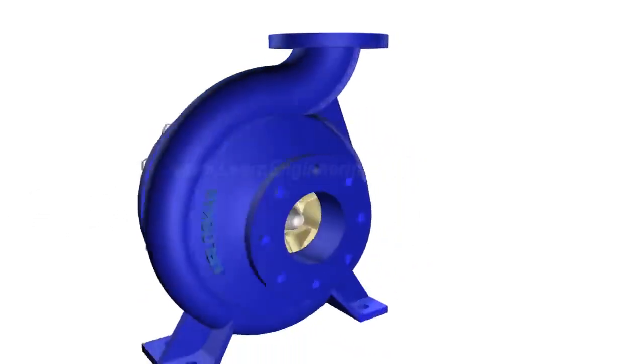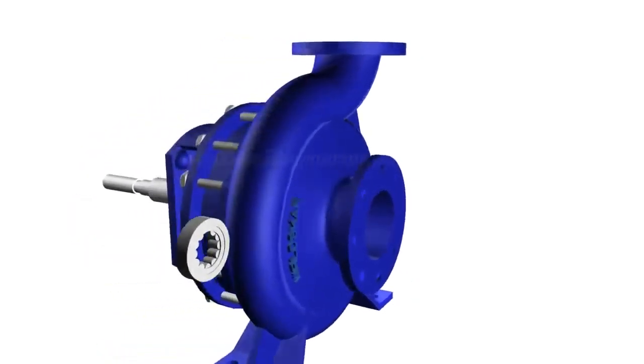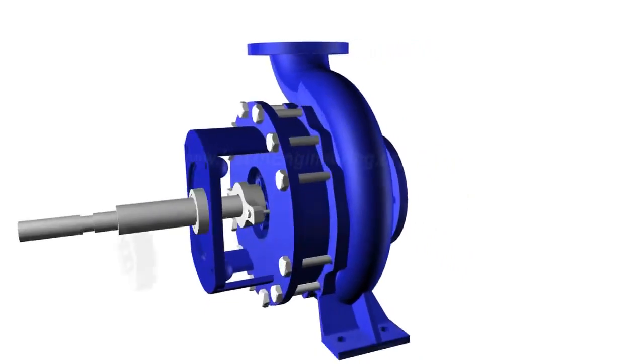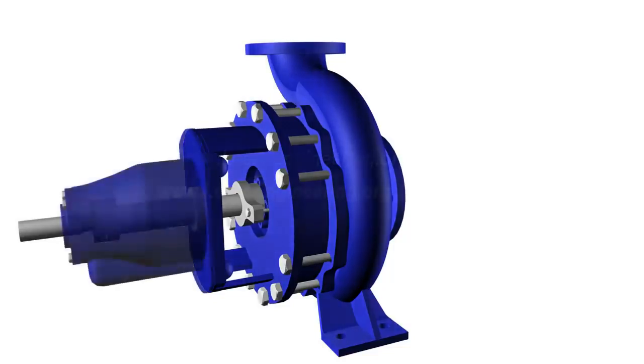The impeller is mounted on bearings, but at suction side of impeller it is not advisable to fit a bearing since it will block the flow. So bearings have to be fitted at the other end. This means impeller is mounted like a cantilever. For high flow rate pumps, a bearing housing with cooling oil is necessary for improving life of bearings.